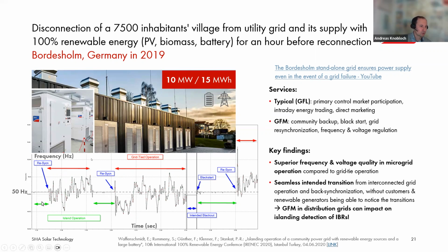So here on the bottom, you see the frequency of the island grid and the frequency where we were connected to the public power grid. It shows you the superior frequency. Voltage quality is not shown here, but there's also a superior voltage quality in this microgrid operation compared to the grid-tie operation. That shows the potential that we have with inverter-based systems if we design them adequately. Yeah, we can improve the power system quality, and it only will depend on the degree of our requirements. How qualitative do we want it to be?